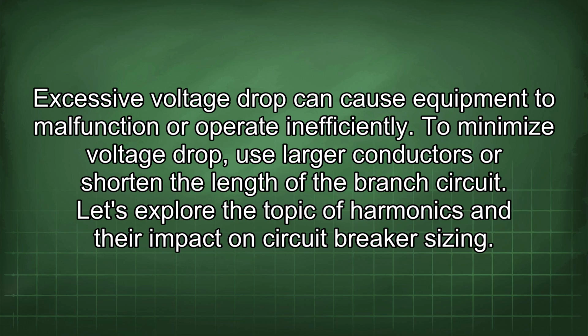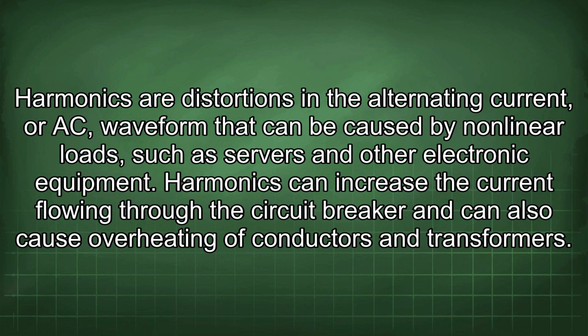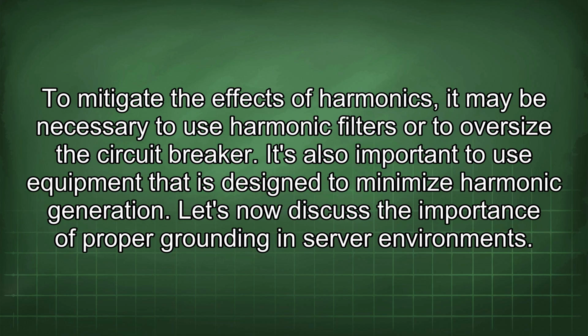Let's explore the topic of harmonics and their impact on circuit breaker sizing. Harmonics are distortions in the alternating current, or AC, waveform that can be caused by nonlinear loads, such as servers and other electronic equipment. Harmonics can increase the current flowing through the circuit breaker and can also cause overheating of conductors and transformers. To mitigate the effects of harmonics, it may be necessary to use harmonic filters or to oversize the circuit breaker. It's also important to use equipment that is designed to minimize harmonic generation.